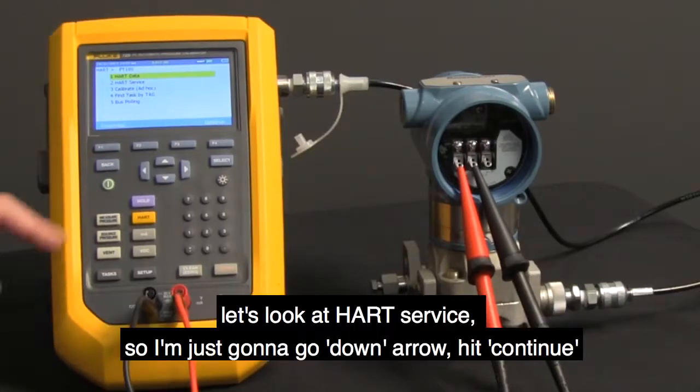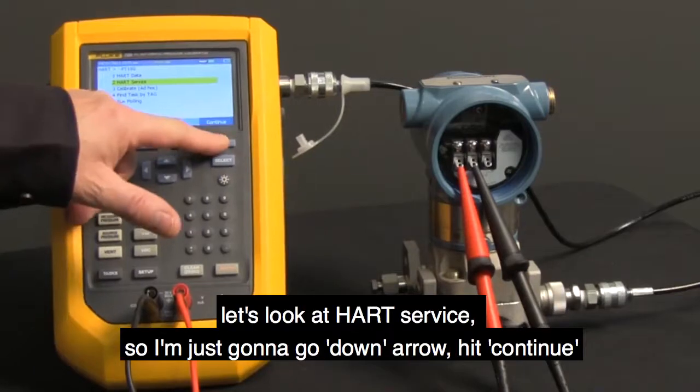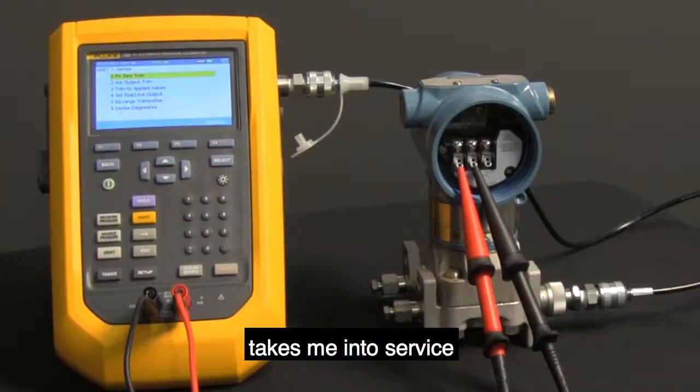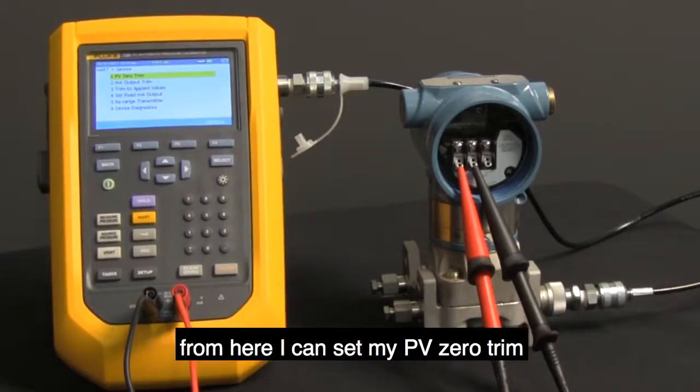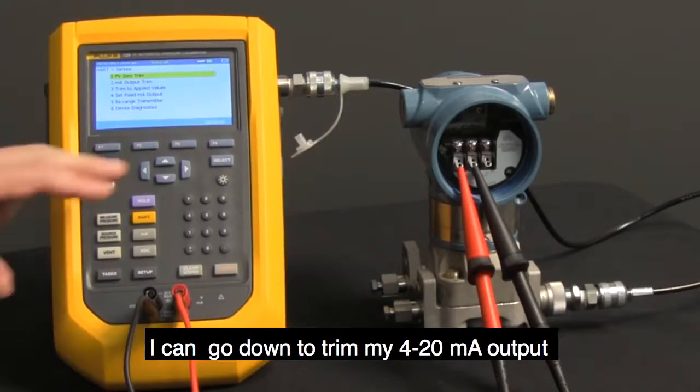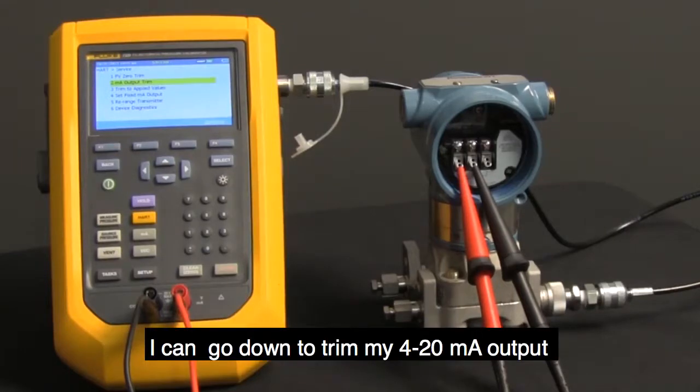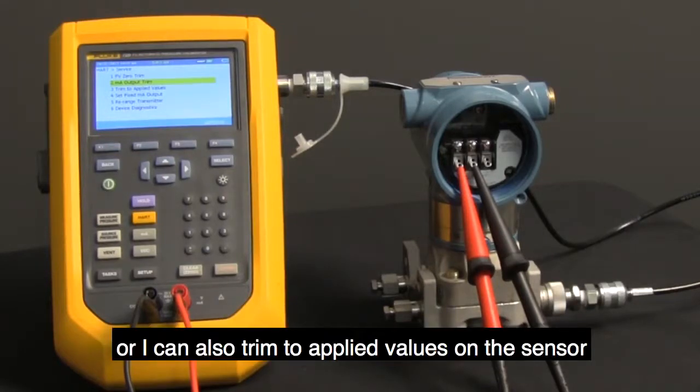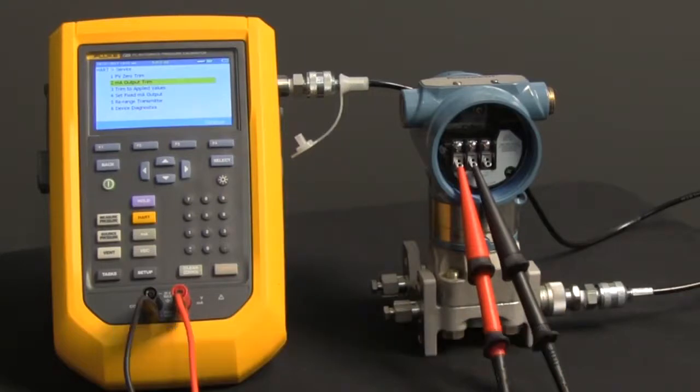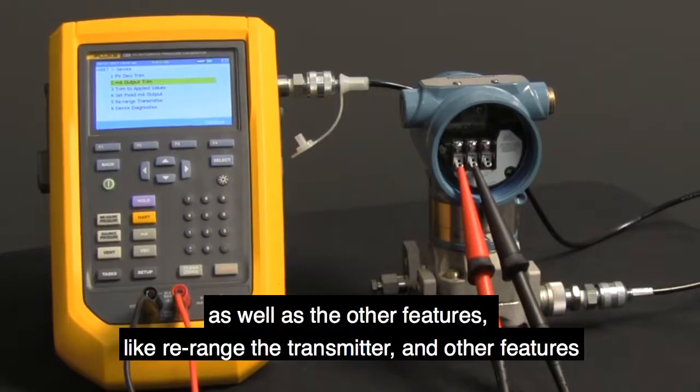Let's look at HART service. So I'm just going to go down arrow, hit continue. It takes me into service. From here, I can set my PV zero trim. I can go down to trim my 4 to 20 milliamp output, or I can also trim to applied values on the sensor, as well as the other features like re-ranging the transmitter and other features.